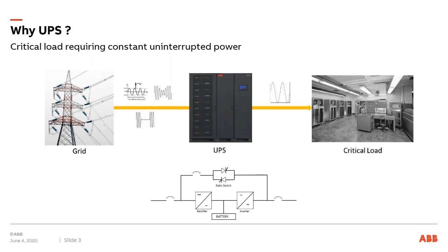So that's the basic functionality. That's what makes the UPS and what makes it uninterrupted. There's one last power module in all major UPSs today that's referred to as a static switch, or static bypass switch. And it's, for lack of a better word, a save-the-day device. The static switch is part of the UPS.